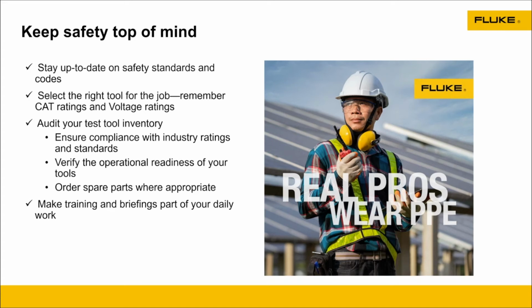As we mentioned earlier, make sure you have the right meter for the right environment. If you've got those older DMMs and clamp meters, you may want to look at retiring them based on those category ratings and get into some newer ones that are safer and they're going to withstand that transient. But make sure they're operational ready. Do that live-dead-live test when you're out in the field. And then if you need to order parts, test leads are cheap. Again, it's an extension of the energy that you're making that measurement to do your job. So replace those test leads at a regular interval. Make sure your fuses are working correctly because again, that is a safety feature in that. And make training and even briefings part of that daily workflow. I know in some environments they do a weekly safety meeting, just looking through and keeping safety at the top of the mind.